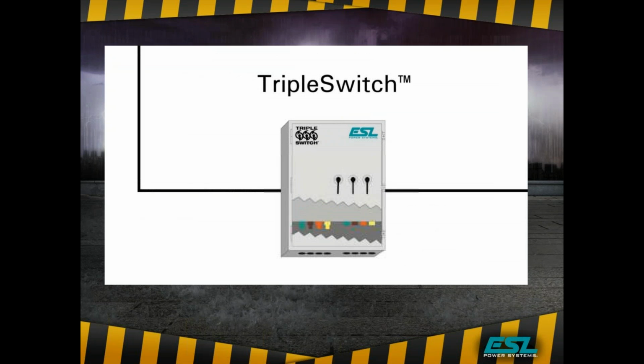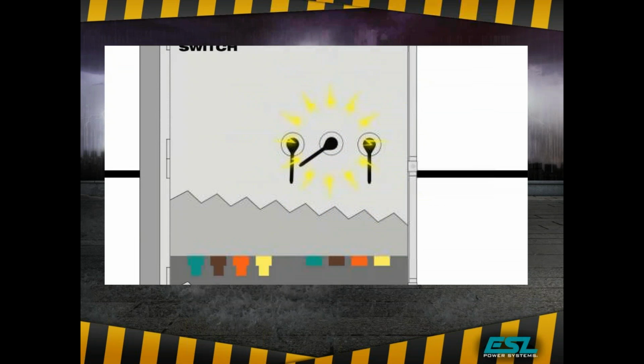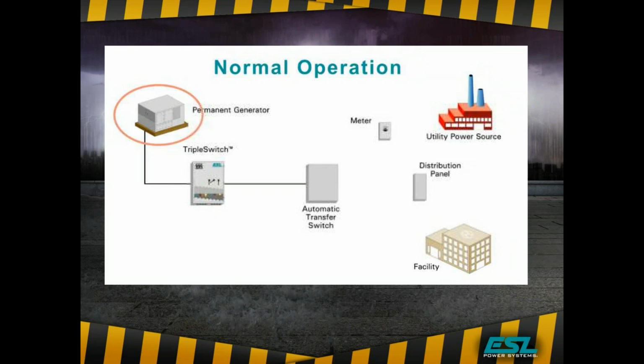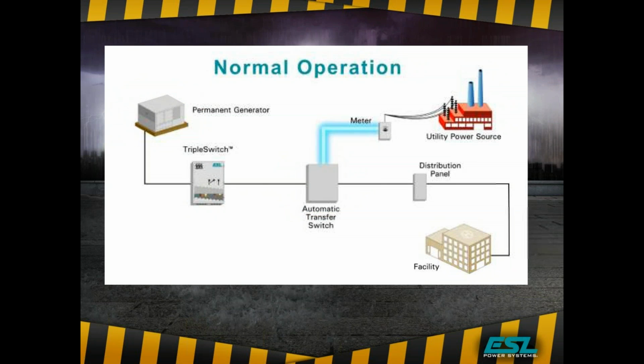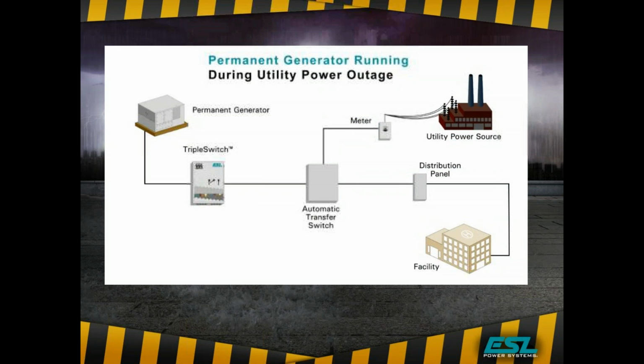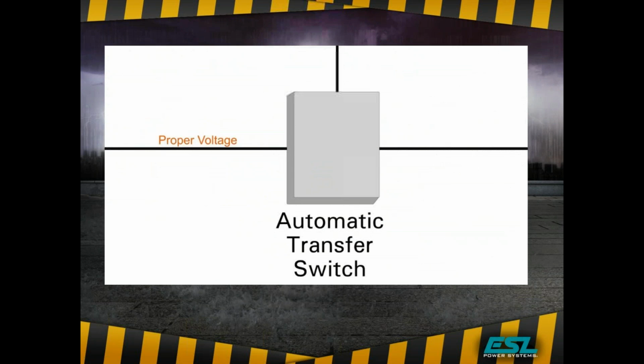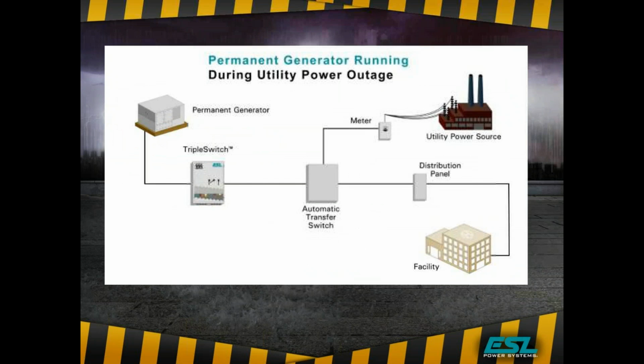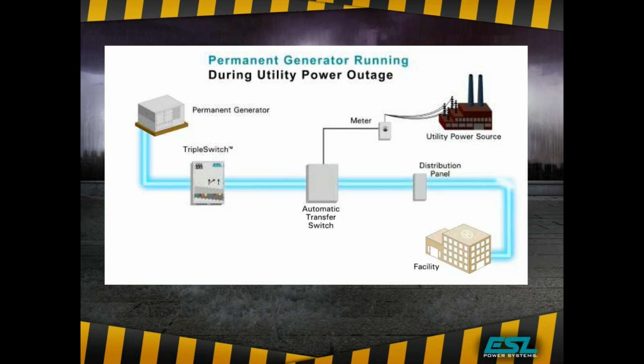Under normal conditions, the center breaker is turned on, connecting the permanent generator to the facility ATS. Utility power flows normally through the meter, ATS, and distribution panel into the facility. During a utility power outage, a startup signal is sent from the ATS to the permanent generator. Once the ATS detects proper voltage, frequency, and phase sequence, the ATS switches over and power is then provided by the permanent generator.